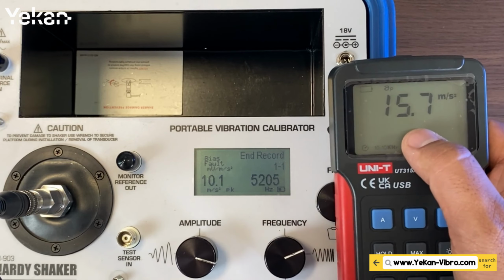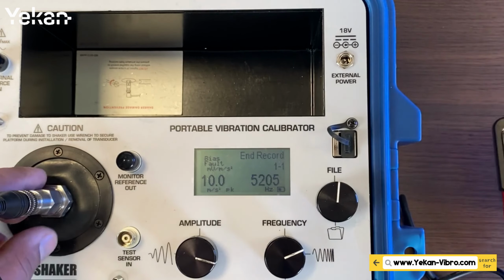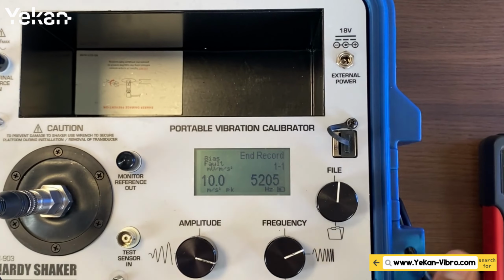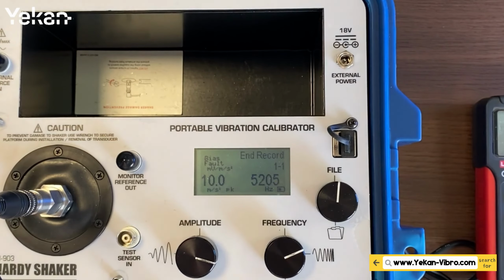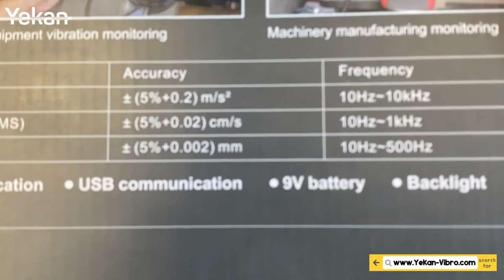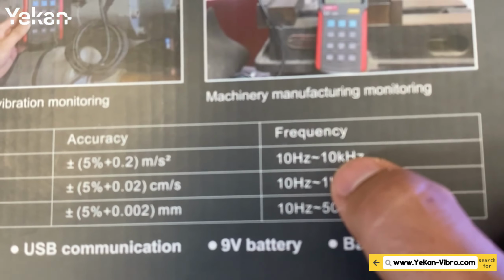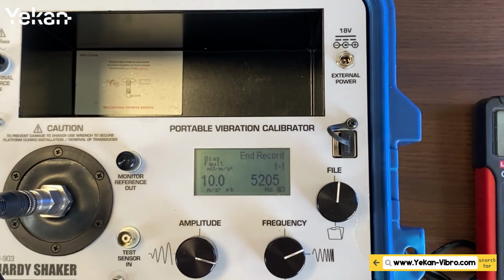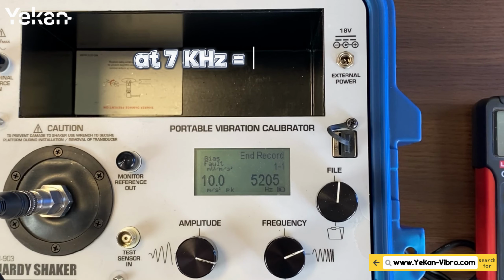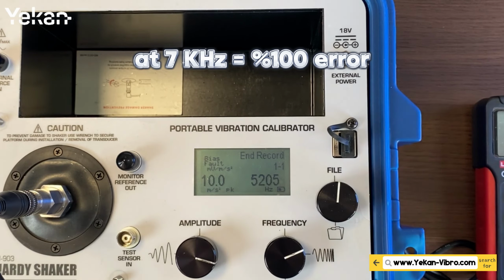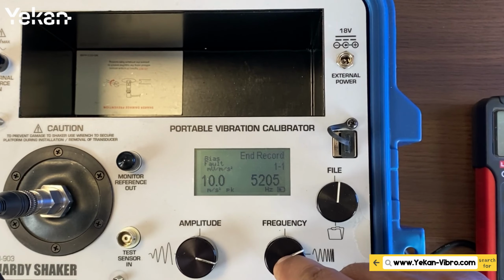You see now in its box it was written up to 10 kHz. It was supposed this equipment works. In its box it was announced up to 10 kHz. But at 5 kHz you saw it had 40% error. And I tested at 6 kHz, 7 kHz it becomes more. Maybe at 7 kHz it reaches 100% error. The best working range of this device is almost up to 3 or 4 kHz.